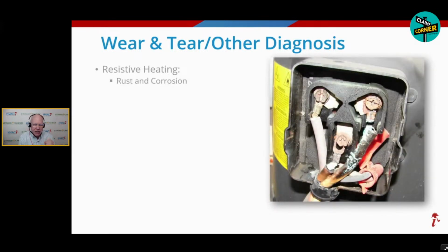So let's look at some resistive heating. These are the terminals of a compressor, right? Look at that white wire on the left, good condition, no problems, right? So resistive heating can be caused by rust and corrosion. That's slowing down the flow of electricity. Look at those other two wires. The one in the middle also has a bad connection, and the one on the right, it's all rusty, right? So which came first, the rust or the corrosion? It was rusty. Then we've had resistive heating. If it's within 1 to 2 inches of a connection and the connection's rusty, that is not lightning and that is not surge. That is resistive heating. All right. So look how many times those wires, every time it cycled on and off, they got hotter and cooler, hotter and cooler. It actually melted the insulation around the wire, and it finally failed.